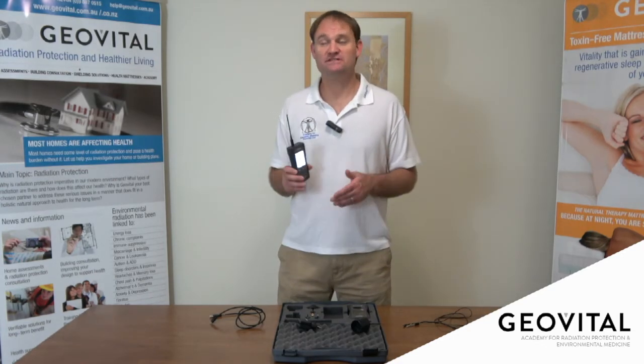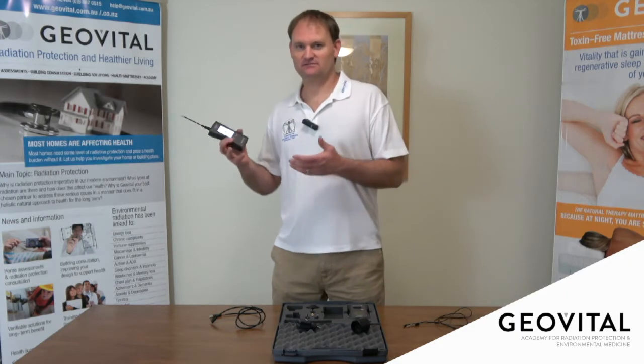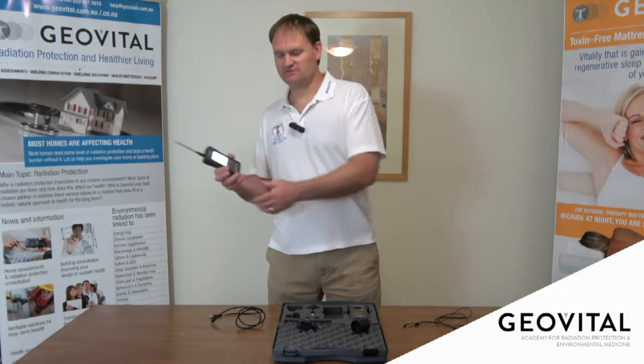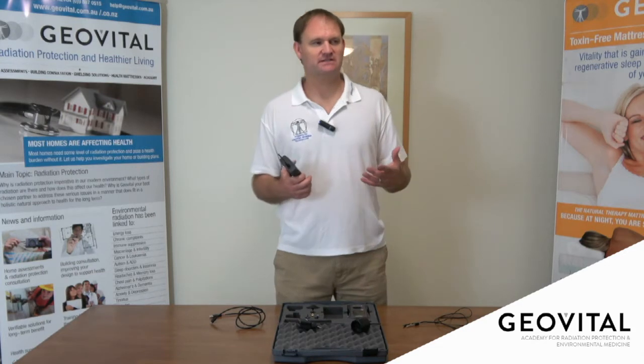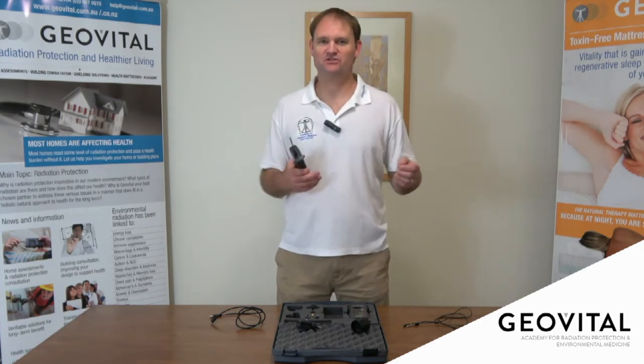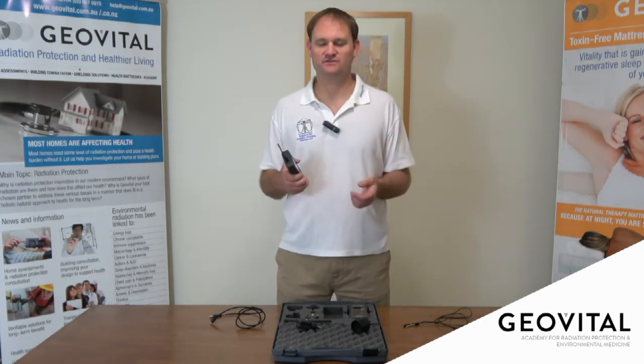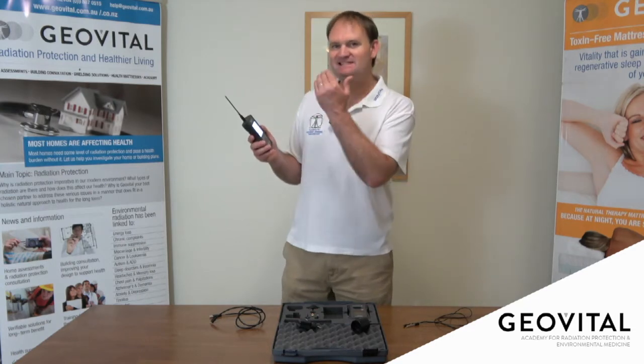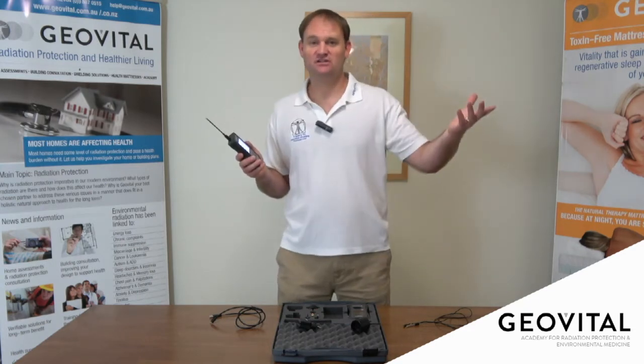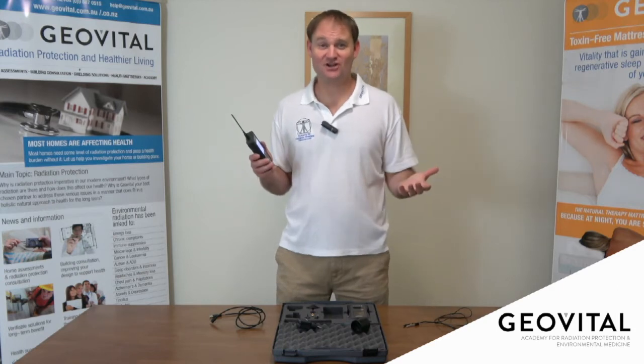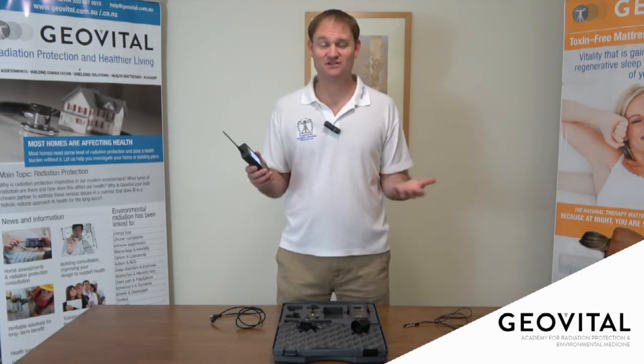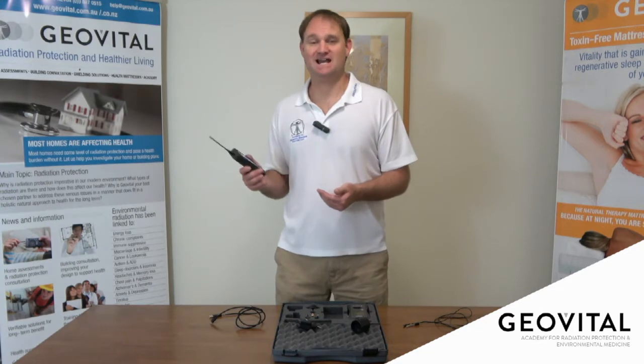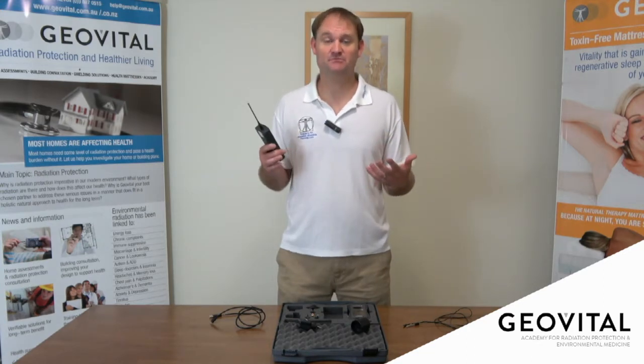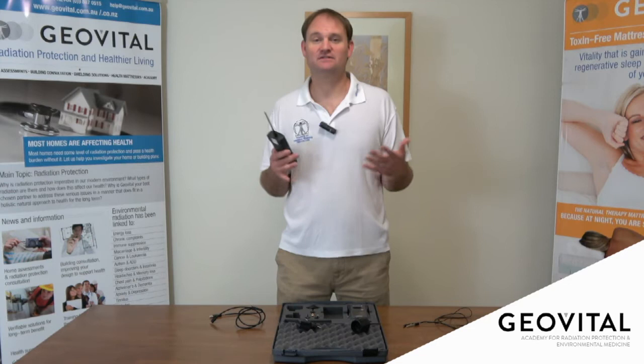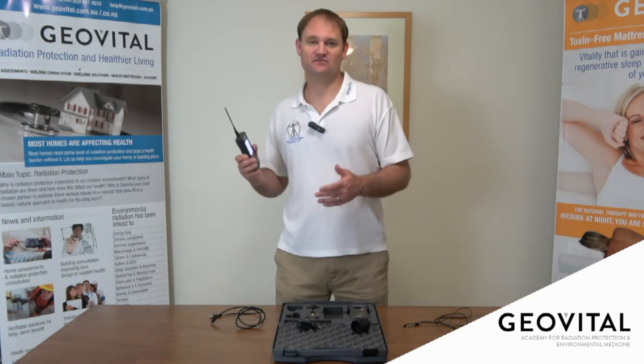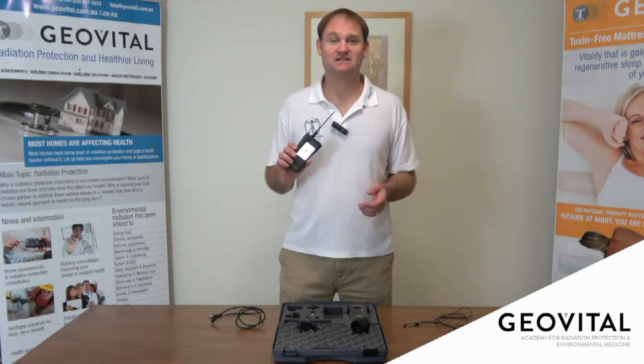Where this is helpful is that if somebody is taking the assessment and seeing what values you get, and the other person is at the circuit breaker panel doing some testing, which our consultants can do with you, then the sound can give an indication at quite a distance of what goes on. If there's no sound, the level is nice and low, it's under 30. If the level goes higher and passes 100, we hear the beep, beep, beep being put on top, and so we already know without a word being said that that level is higher than 100, which helps in the assessment process.